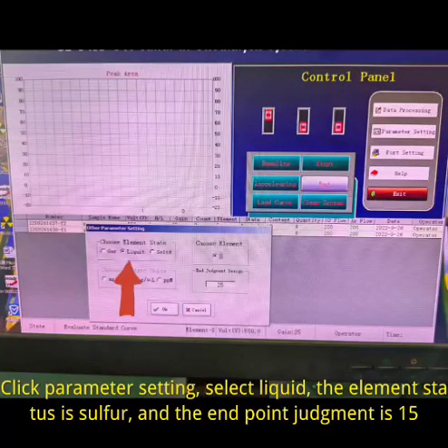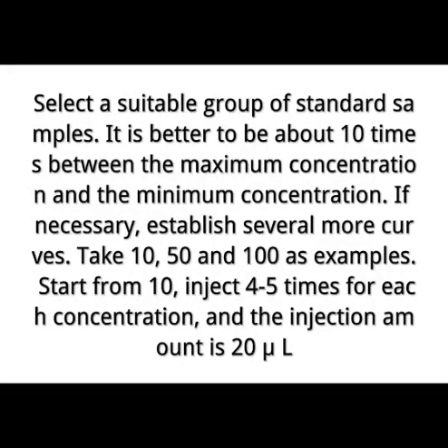Click Parameter Setting, select Liquid, the element status is sulfur, and the endpoint judgment is 15. Select a suitable group of standard samples. It is better to be about 10 times between the maximum concentration and the minimum concentration. If necessary, establish several more curves. Take 10, 50 and 100 as examples.